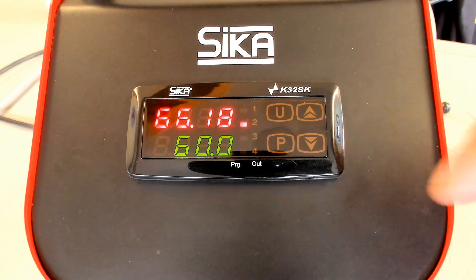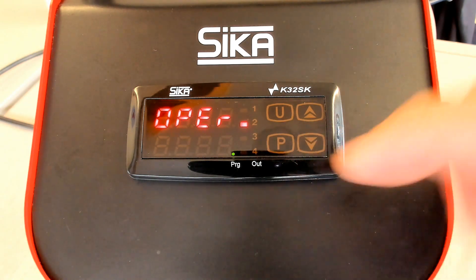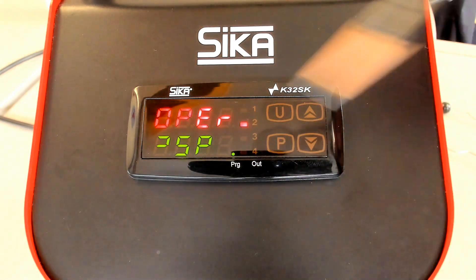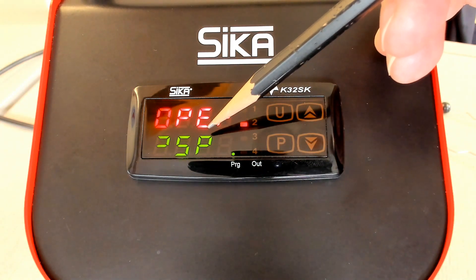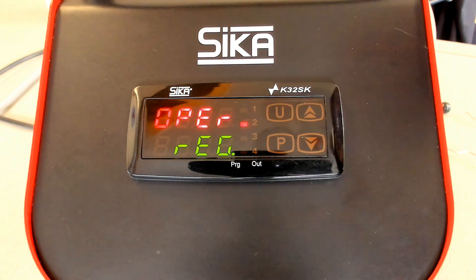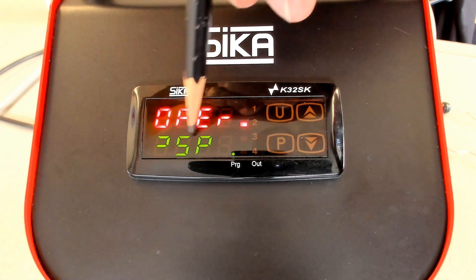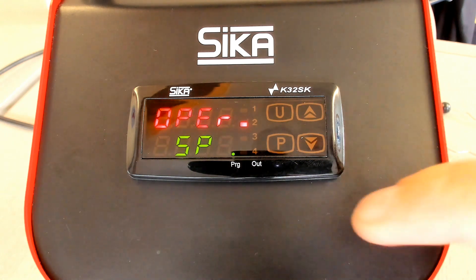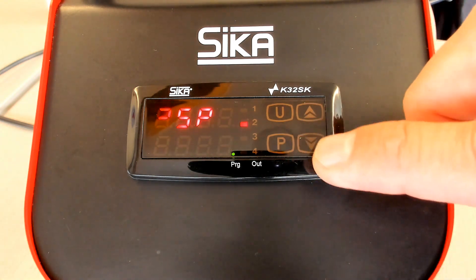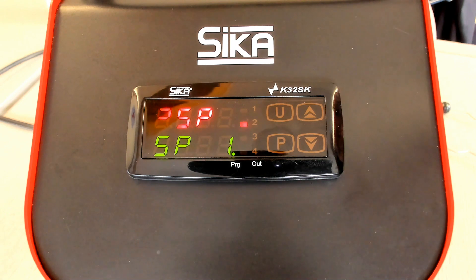Last but not least, we have another content of the main menu — OPEr, which is the operator menu. The operator menu has different content: we see SP for set point, ENP for input, and REG for regulation. In the set point group, you go in via the P button, and in the set point group you can select different parameters because you have the possibility to program up to 4 set points in the calibrator.